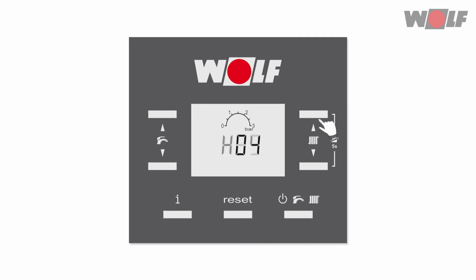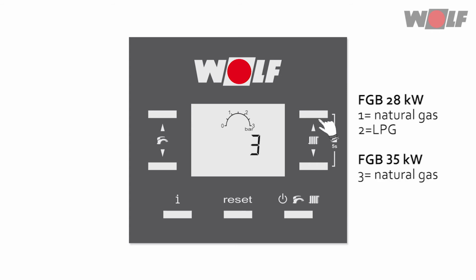Parameter H04. The parameter H04 is the setting for the maximum burner output in heating mode. It applies to the heating mode, cascade, and emission test. This percentage value corresponds approximately to the real device output. Parameter H12. In this parameter, the gas type used for the gas condensing boiler can be set to 1, 2, 3, 4. When changing the gas type, it is imperative to observe the chapter Determining or Changing the Gas Type. Never change the appliance output, as this can lead to appliance damage or faults.